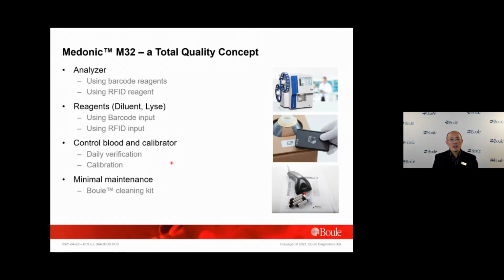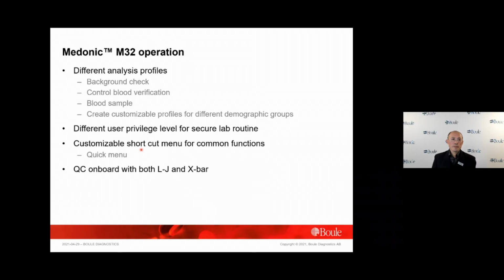Control and calibrator blood are a very important component of the total quality system. Calibrator is designated to calibrate the instrument, and the control blood is used to verify the instrument result. We will talk shortly about the difference between them and the case when each one should be used. And next, we will go through some issues or highlight some points for the M32 operation.